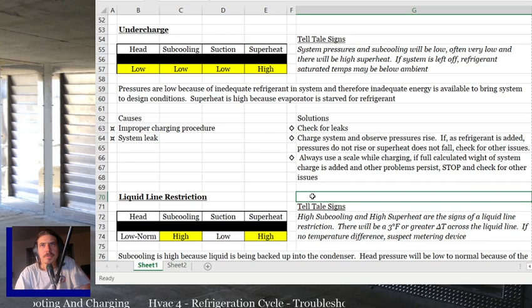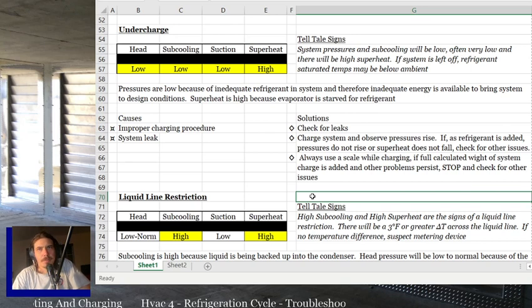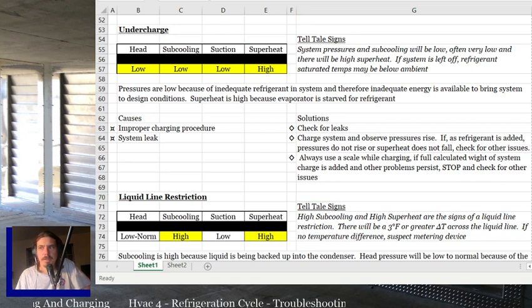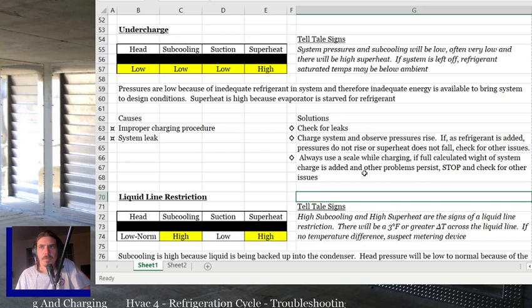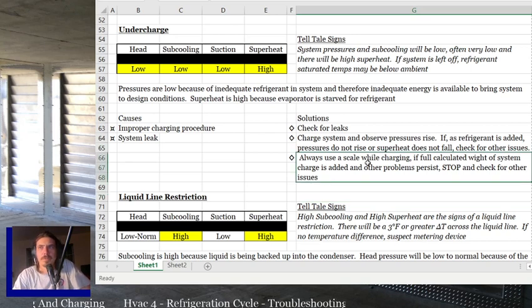next issue we could run into is an undercharge. Next one on our list anyway, right? On an undercharge, head pressure is going to be low, subcooling is going to be low, suction pressure is going to be low, superheat is going to be high. You have to take all those into account to determine if you got an undercharge. All right, all those are going to be important values. System pressures and subcooling will be low, often very low, and there will be high superheat. If the system is left off, refrigerant saturated temps may be below ambient.